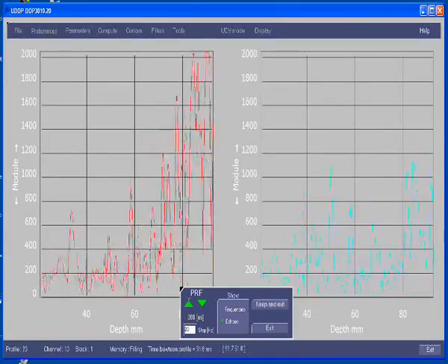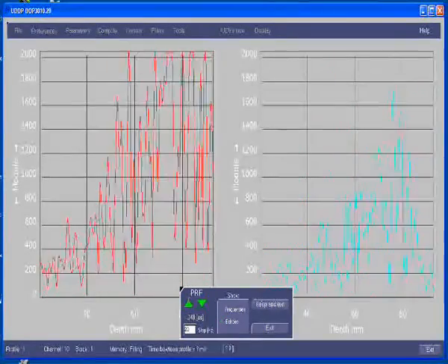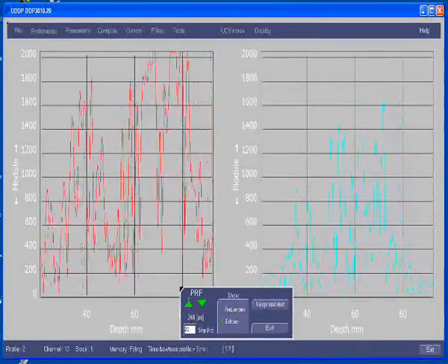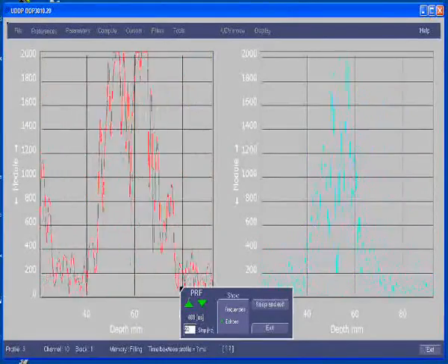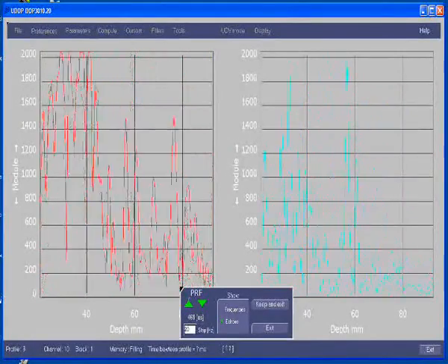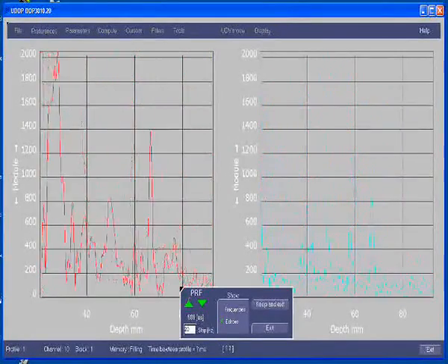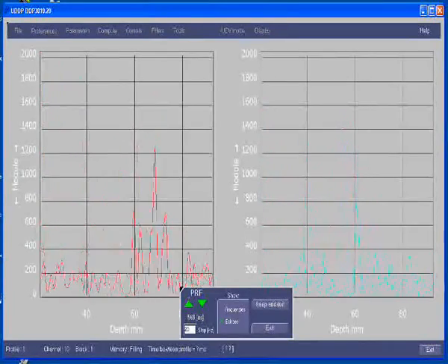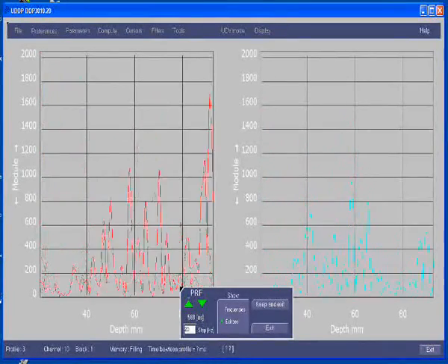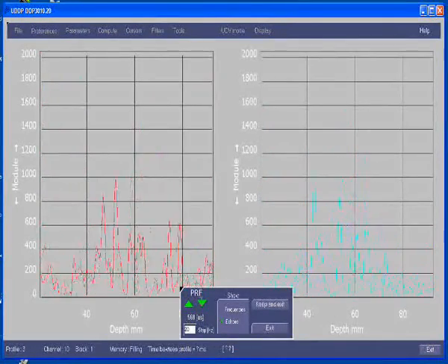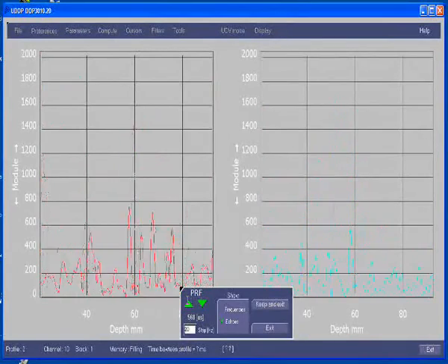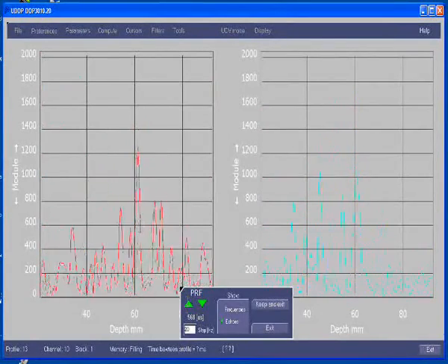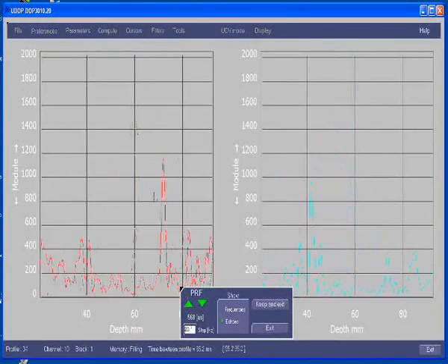As you may realize, for some specific values of the PRF, strong echoes appear in the echo profile. A good PRF value is one for which small changes around its value do not imply any changes in the echo profile. It seems to us that the value of 568 is a good value, so we will keep that value.